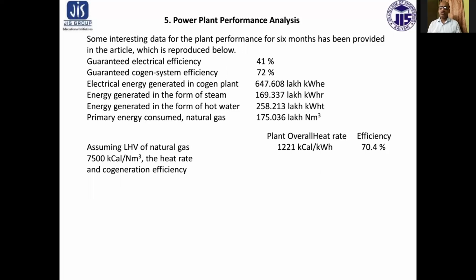Primary energy consumed, that is natural gas, is 175.036 lakhs cubic meter. The plant overall heat rate and efficiency is given, with efficiency of 70.4%. Assuming a lower calorific value of natural gas of 7,500 kilocalorie per cubic meter, the heat rate and cogeneration efficiencies are simultaneously given.